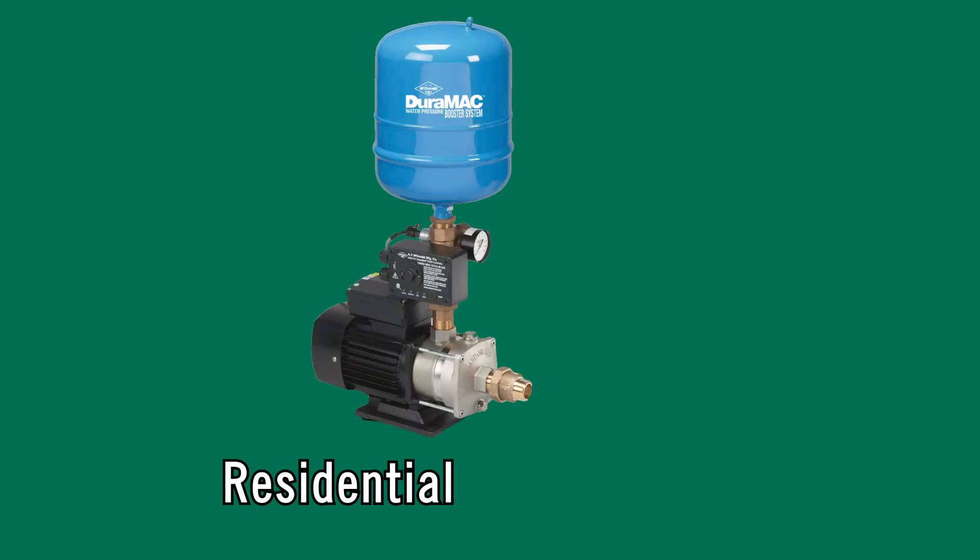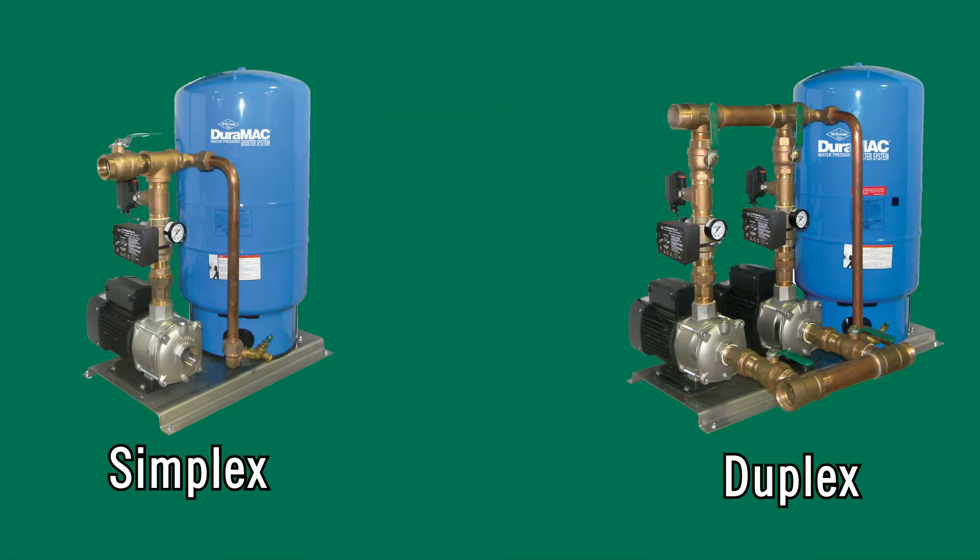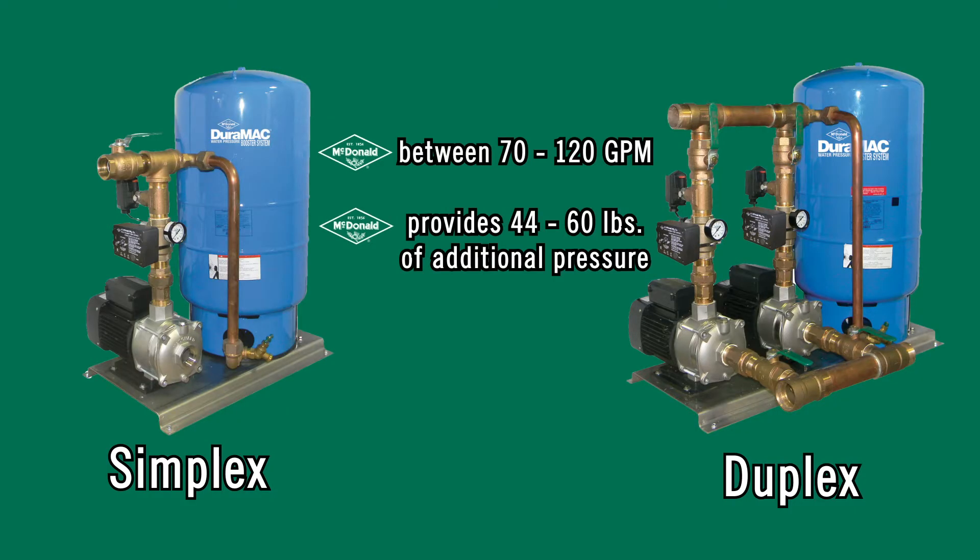Residential and light commercial booster pumps reach up to 35 gallons per minute and give you 35 to 78 pounds of additional pressure. The DuraMAC simplex and duplex systems are capable of reaching between 70 and 120 gallons per minute and 44 to 60 pounds of additional pressure.